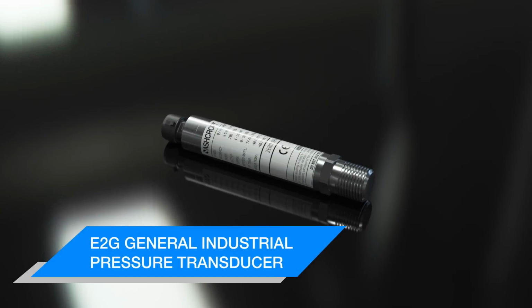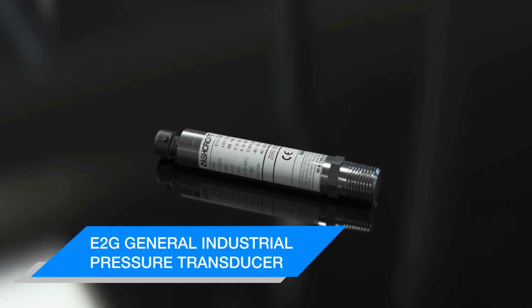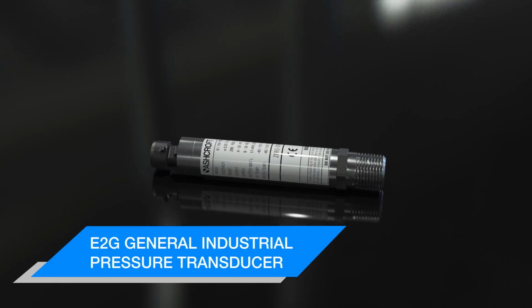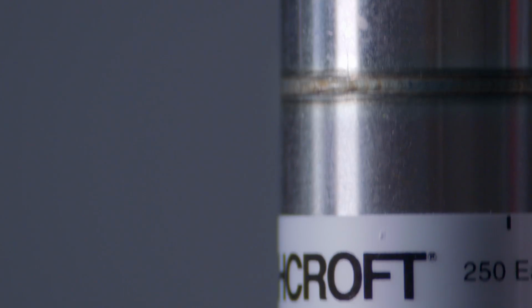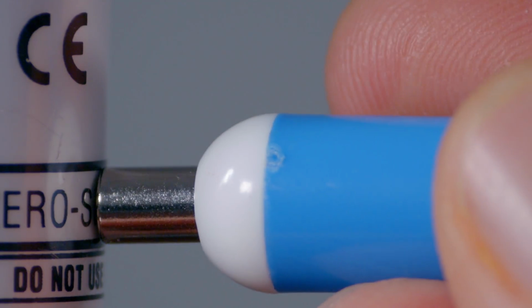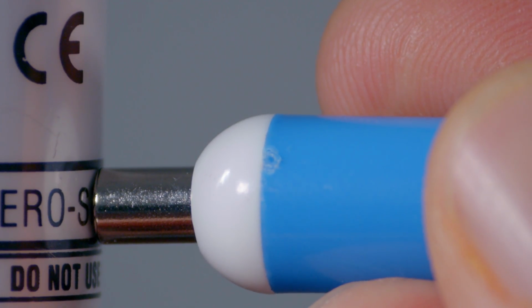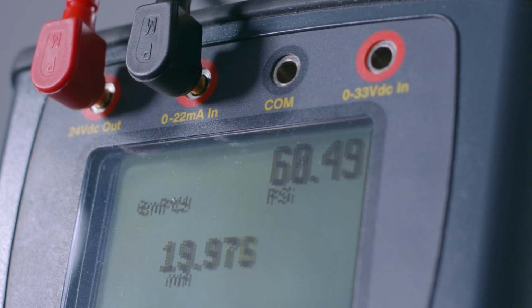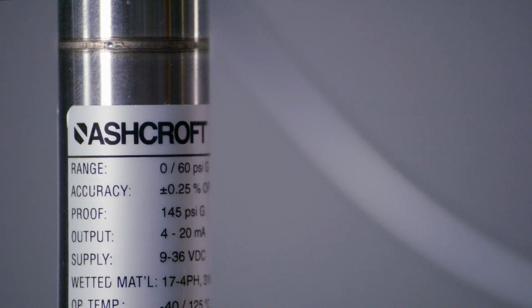The Ashcroft E2G General Industrial Pressure Transducer provides a unique way to adjust offset and span without ever having to open the sealed housing. By using a magnet to operate an internal reed switch, the transducer can be calibrated externally without exposing the electronics to moisture and contaminants.